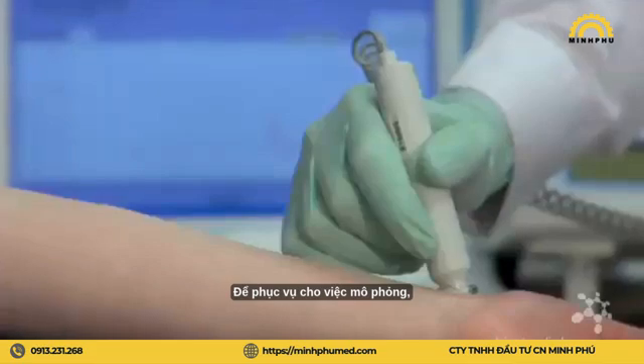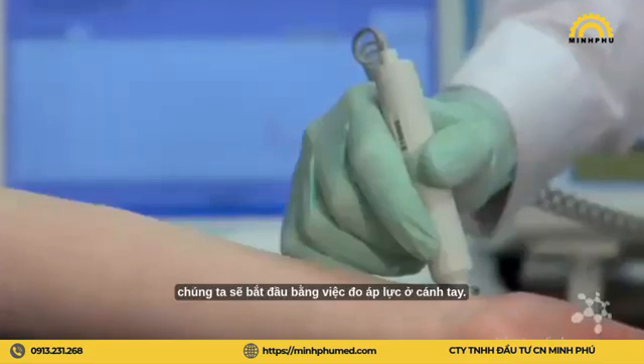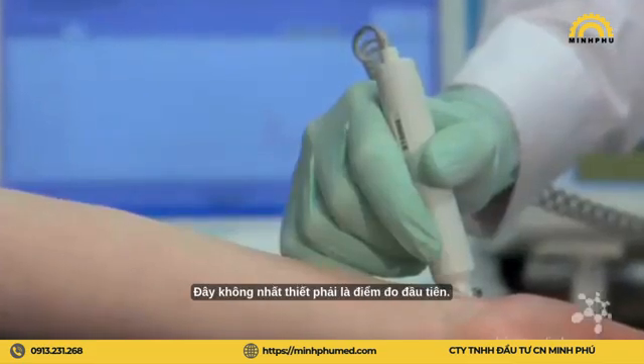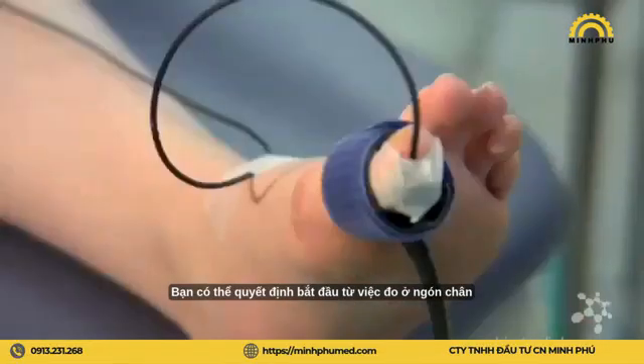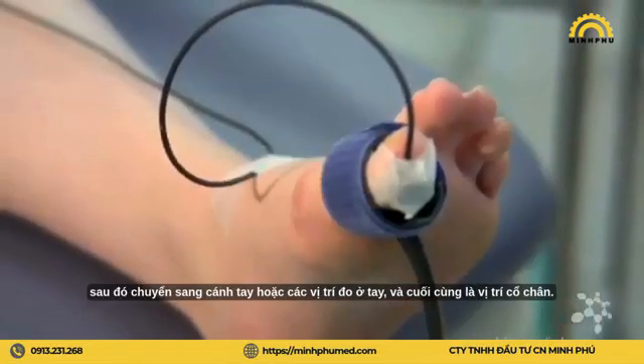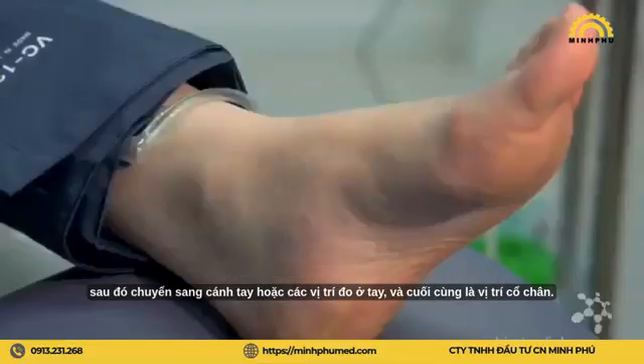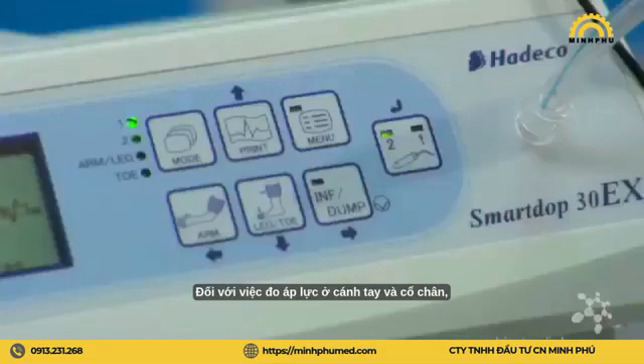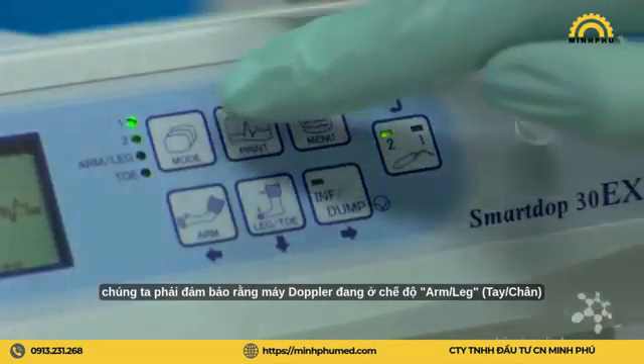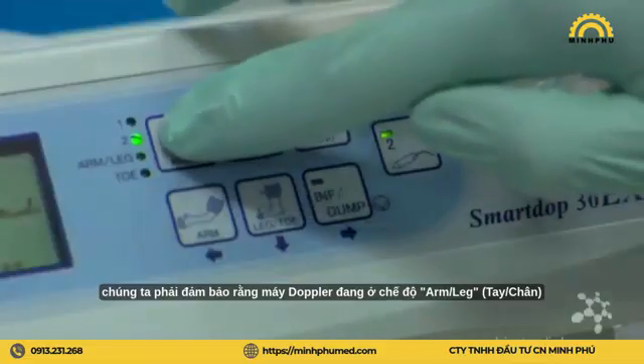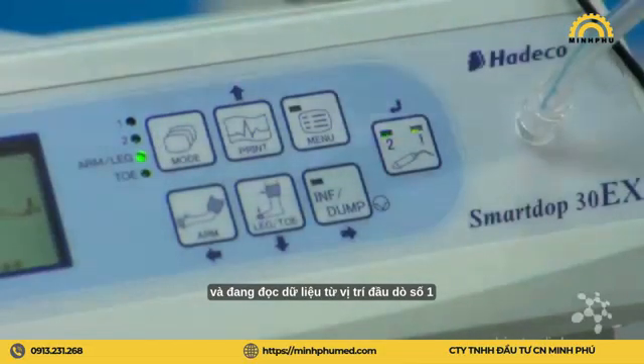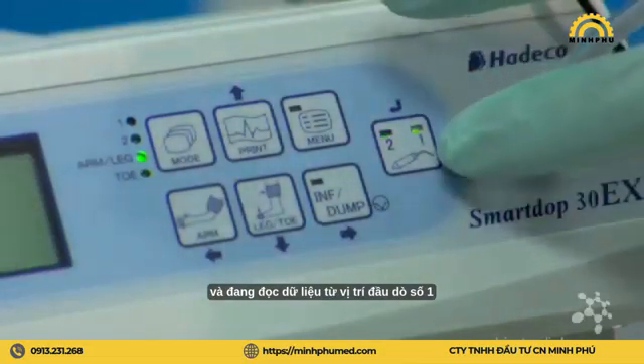For the purposes of this demonstration, we shall start by obtaining a brachial pressure. This does not have to be the first pressure point taken. You may decide to start with the toe pressure and then move to arm or brachial positions, followed by the ankle position. For brachial and ankle pressures, we must ensure that the Doppler is on arm-leg mode and is reading from the probe position number 1, where the 8 MHz probe is attached.